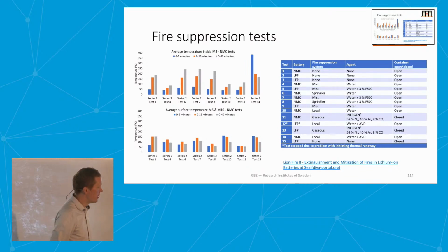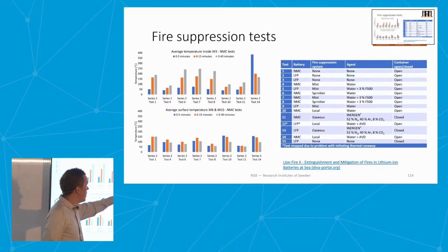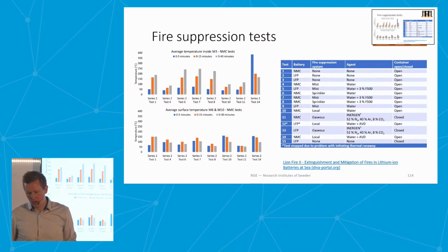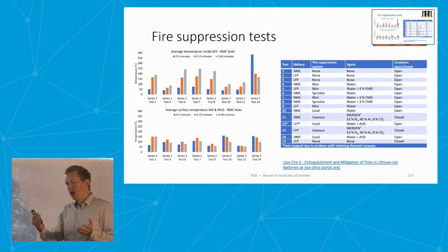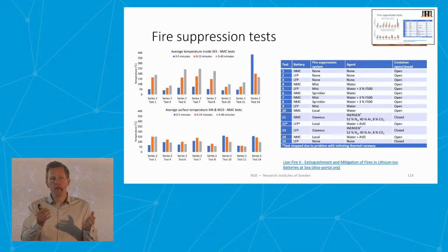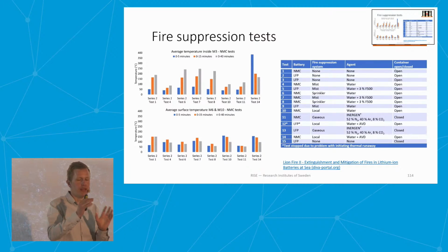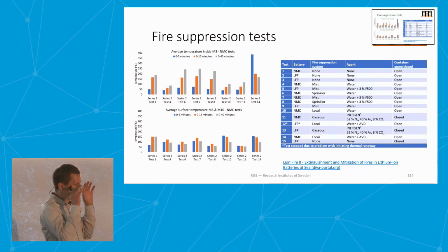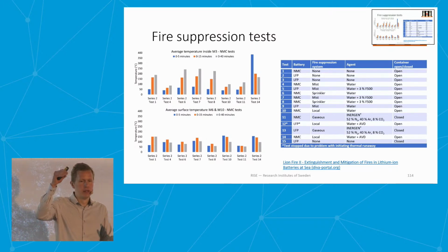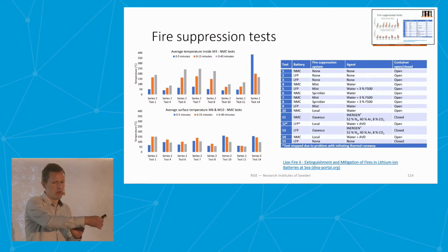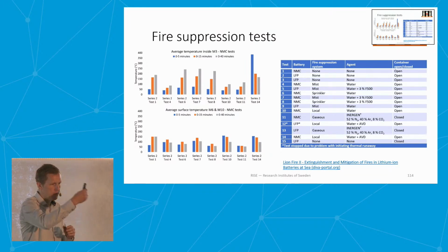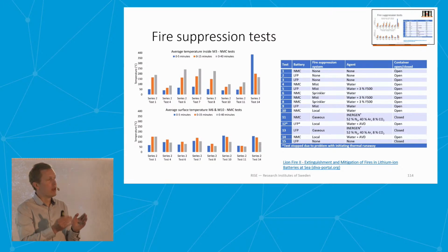That could also be seen in this test—the AVD—because with the AVD you get some insulation as a heat barrier, but that was only applied on the front of the module in this case, since you had the sprinkler there. So you don't get access to the back of the module, and then you had the flames on the back, transferring heat to that module, and the insulation on the front actually increased the temperature of that dummy module.